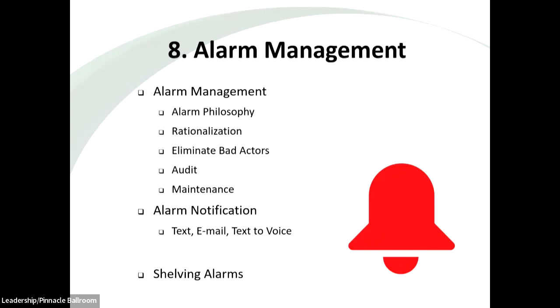Alarm management. One feature of SCADA systems is alarm management. The whole vision of alarm management is to make sure that alarms, when they come up, actually mean something. A lot of times one alarm triggers a sequence of events that create more alarms, and all of a sudden your alarm summary grows very fast. What's important is the first one that started that sequence. Alarm management is the process that hides all the alarms that are a result, and only lists the very first one. That's the idea behind alarm management.